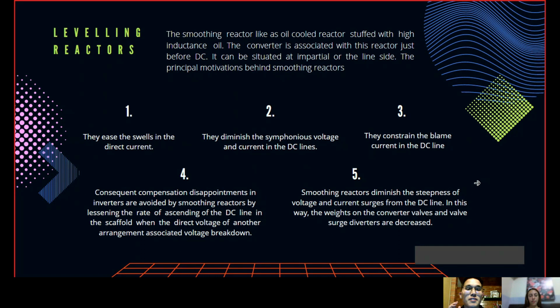Smoothing reactors. The smoothing reactor, like all such reactors filled with high-insulation oil, is connected with the converter just before the DC line. It can be situated at the neutral or the line side.